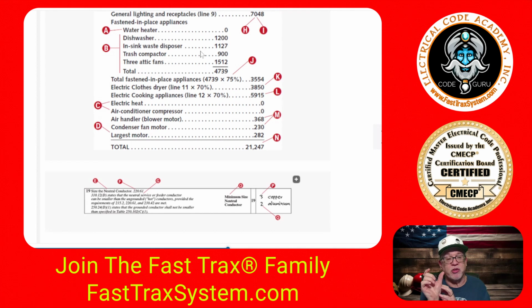And that's all we're trying to do, because we're taking, as a neutral load, that in-sink waste disposer at 125%. Well, since we took it at 100, even though we did apply some additional demands to that, we took it at 100 originally, we just need to capture that additional 25%. And that's what goes right there. That makes sense? And it's the same thing we do when we're sizing the hot conductors, okay?